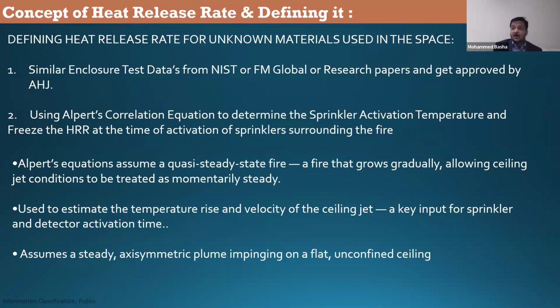Or if you don't know what is going to be in that space, for example, you are building for a tenant, he tells, I want a stage. Okay, fine, stage. But what is going to happen in a stage? It's going to be a music concert stage, or it's a film screening. We don't know anything, right? So we don't know what materials are going to burn either. So if we don't know what materials are going to burn, then how can we design a smoke management system? That is where Alpert's correlation equation comes in. This Alpert's correlation equation is taken from the SFPE handbook, Society of Fire Protection Engineers handbook, volumes 3 and 5. It helps us to determine the Q value in a different way. What is a different way? This will work only if you have a sprinkler, which is called a sprinkler-controlled fire. We have discussed this in the previous slides before.